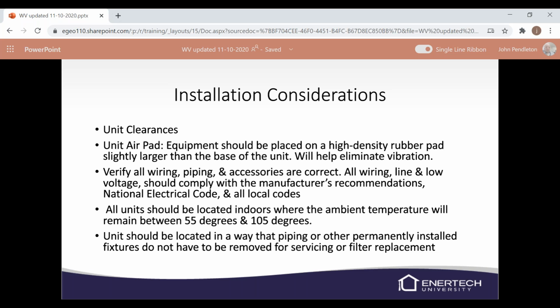Make sure you always verify the wiring and piping and accessories are correct and that they're wired in properly. Double check your low voltage wiring on the control side of things. And make sure you're always following your national and local electrical and plumbing codes. The unit, again, needs to be located indoor with an ambient temperature that should range anywhere from about 55 to 105, and located in a way that piping or other permanently installed fixtures do not have to be removed for servicing or filter, or for like your case filter. Don't put a copper pipe running right in front of it. Don't run piping right in front of your doors where you have to get access to the unit as well.